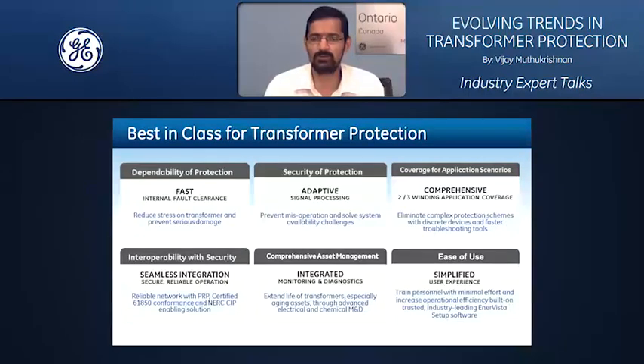Now the third one comes into the picture as you have a variety of transformers. You may have an old system in which the protection systems are discrete in nature. You have multiple relays put together as a scheme and deployed for transformer protection. Can you have a device that can converge these applications and meet all your variety of application needs, all the way from 2-winding, 3-winding, or even multi-terminal transformer applications? That is the third pillar when it comes to best-in-class transformer protection.